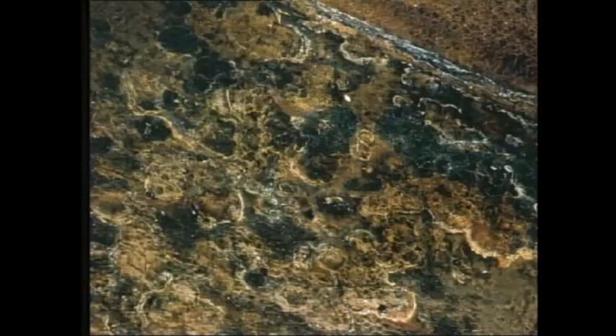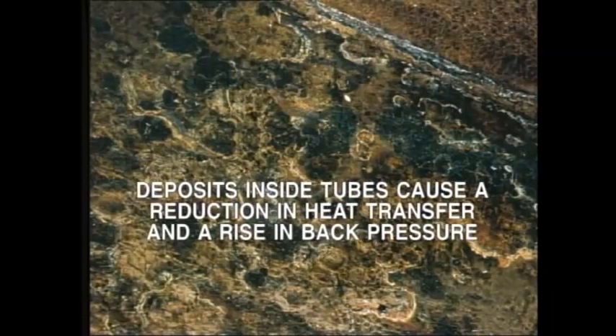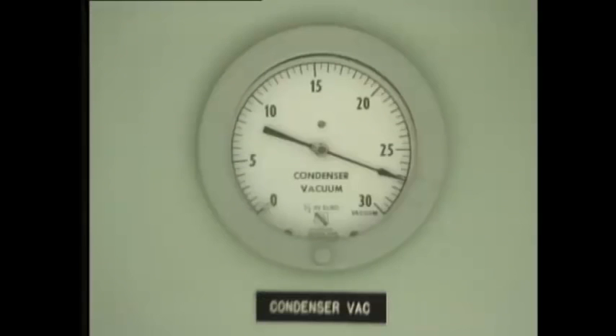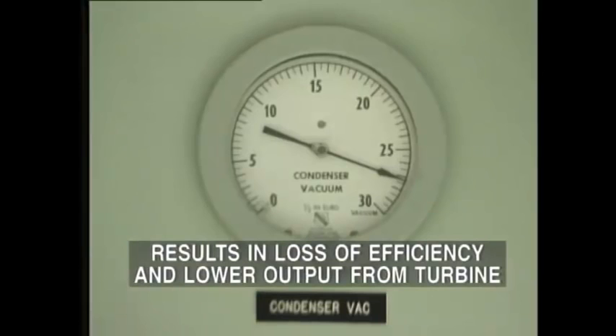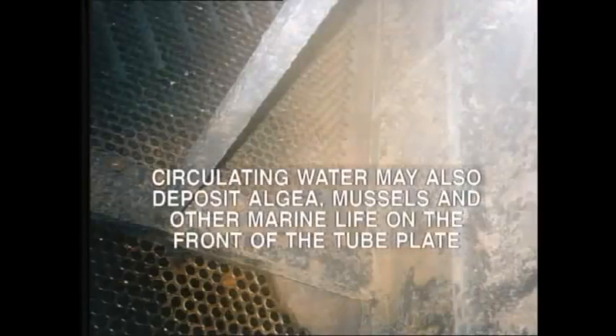Over a period of time, the circulating water may leave some deposits inside the tubes. The consequence of this is a reduction in heat transfer and a rise in the back pressure inside the condenser. This results in a loss of efficiency and lower output from the turbine. The circulating water may also deposit algae, mussels, and other marine life on the front of the tube plate, reducing the flow of water through the tubes. Again, the result is a loss in cooling and a consequent rise in back pressure. Generally, the condenser needs to be cleaned manually from time to time, and in most cases, this entails shutting down the turbine. There are, however, some machines which are designed to allow one half of the condenser to be cleaned, while the other half remains in service, and the unit continues operating at reduced load.